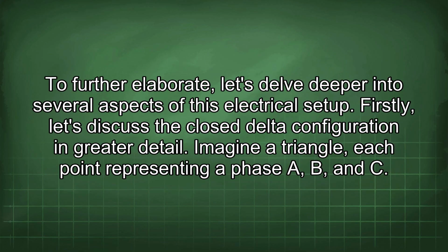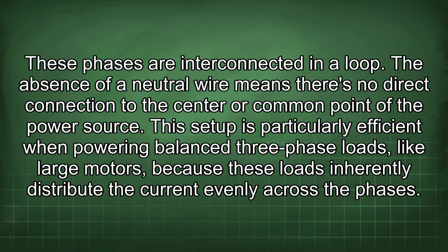To further elaborate, let's delve deeper into several aspects of this electrical setup. Firstly, let's discuss the closed delta configuration in greater detail. Imagine a triangle, each point representing a phase A, B, and C. These phases are interconnected in a loop. The absence of a neutral wire means there's no direct connection to the center or common point of the power source. This setup is particularly efficient when powering balanced three-phase loads, like large motors, because these loads inherently distribute the current evenly across the phases.